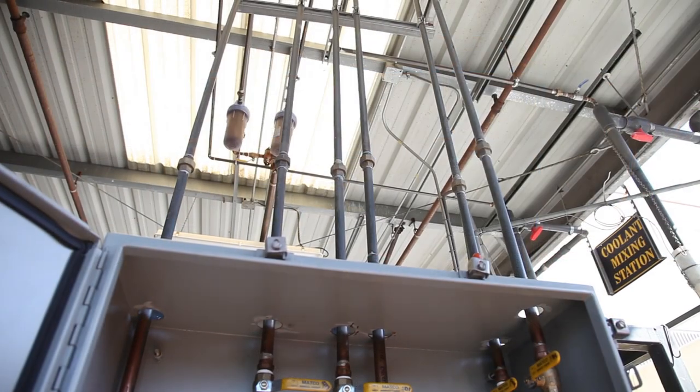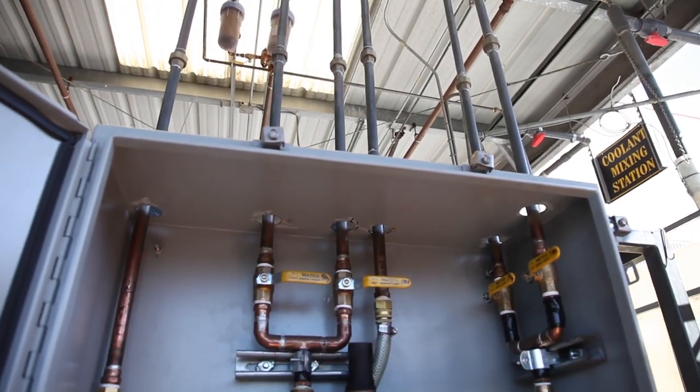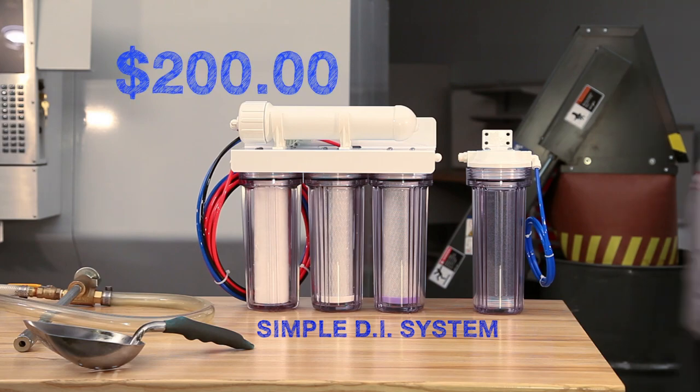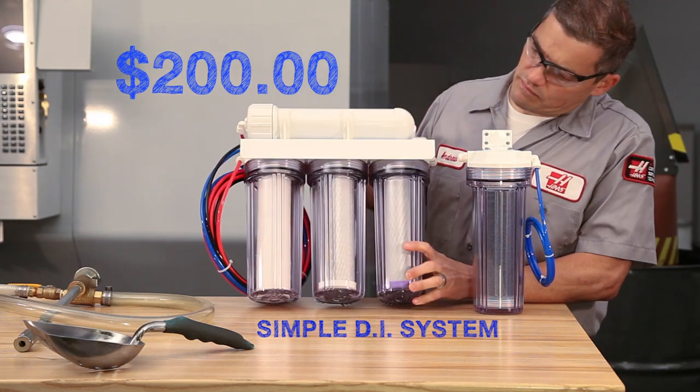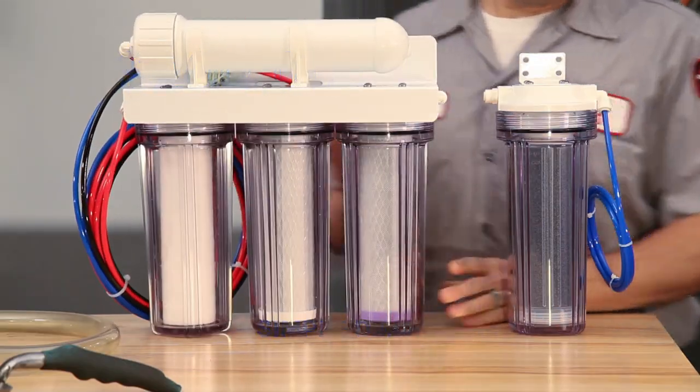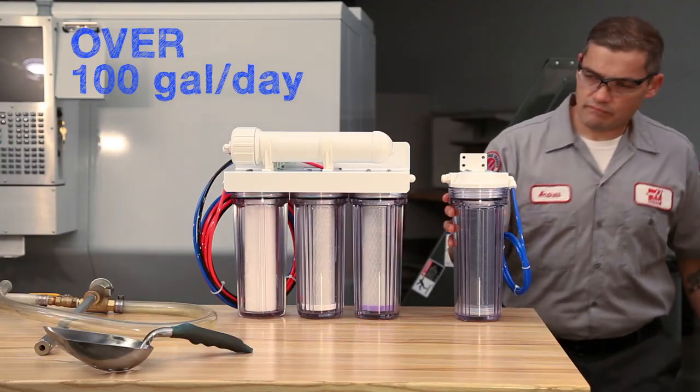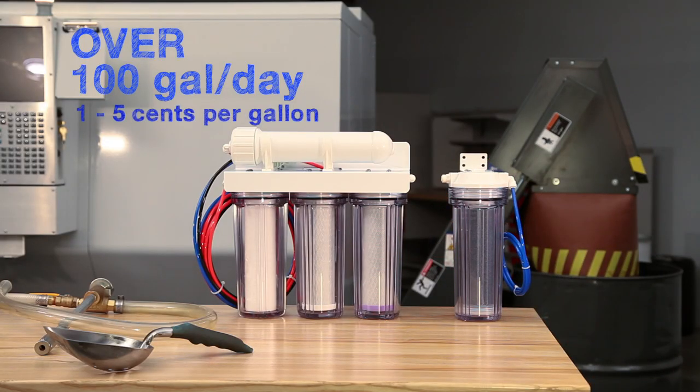Large shops with many machines often have complex installations maintained by water purifying companies. For smaller shops, simple, inexpensive units for a few hundred dollars are usually just fine. These simple systems combine reverse osmosis and deionization and can provide more than a hundred gallons of purified water a day, for a cost of five cents or less per gallon.